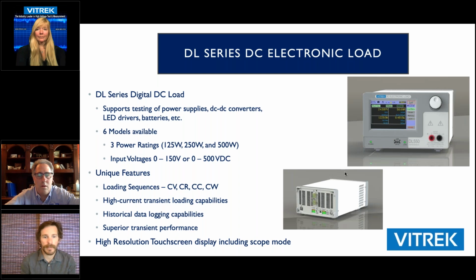What's unique about it compared to other loads is that we have high transient capabilities - we'll get into that later in the slides - but we're able to load kilowatts for short periods of time. We also have a unique scope mode. A lot of other loads lack a detailed graphical interface, and reading the manuals of some competitors, they'll literally say if you want to do this, hook up a scope. In most cases, you don't have to with our load.